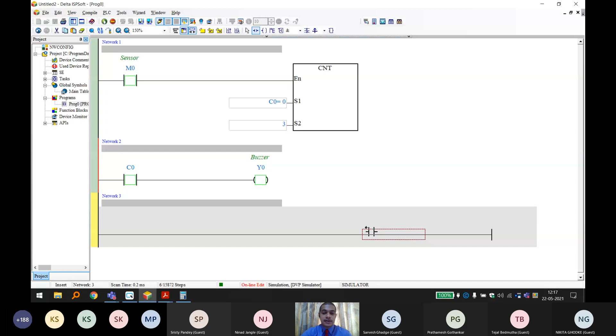And again, in counters, you will have to reset the counter once it is done. So we are going to use another auxiliary relay, let's say M1, and we'll call this reset, and we will reset this counter. So I'm going to put this as a reset coil and put C0 here. Let us update this program and see how this is going to run.